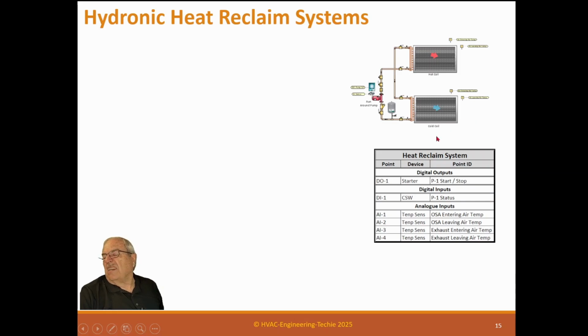So if this is the cooling coil, heating coil, hot coil, cold coil, it depends on what these are. Let's say this is the outside air, and it's wintertime, so we bring in cold outside air. We take the heat out of the exhaust, and we pump it into the outside air to heat up the outside air. If it's the other way around, and this is the outside air, and the exhaust is cold, then we want to take the heat out of the outside air and put it into the exhaust and exhaust it out of the building. So that's the two ways we do that, but it works either direction.